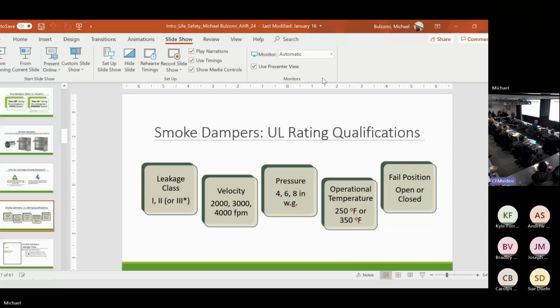If you put a 350 rated actuator for no reason other than it's greater than 250, I now went from an 18-inch pound actuator to maybe 175 or an 80-inch pound actuator, because the heat degradation of the output of the torque to pass at 350 changes the torque requirement of the damper, and then the actual construction of the actuator changes. Instead of using plastic gears, it has to use composite metal gears. So the cost of the actuator skyrockets. So again, you're not getting any additional safety benefits by over specifying a life safety damper.